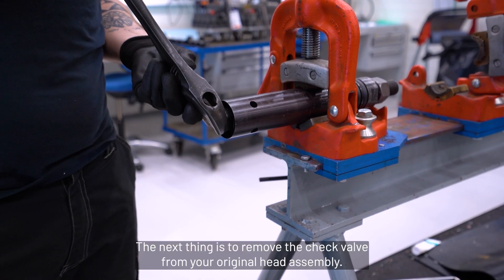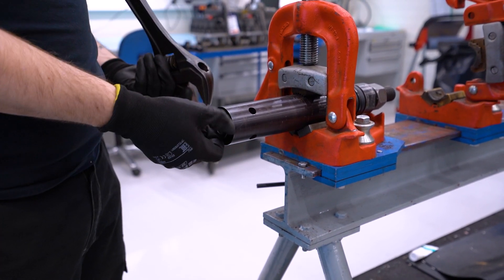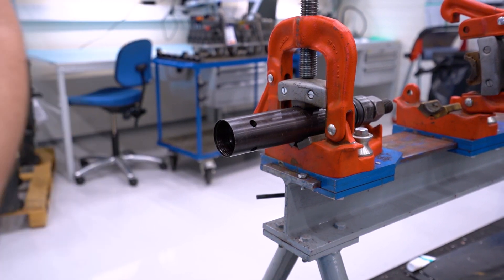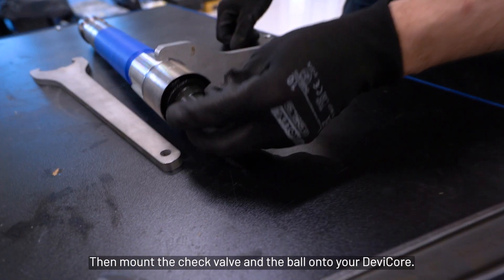The next thing is to remove the check valve from your original head assembly. Remove both the check valve and the ball, then mount the check valve and the ball onto your DeviCore.